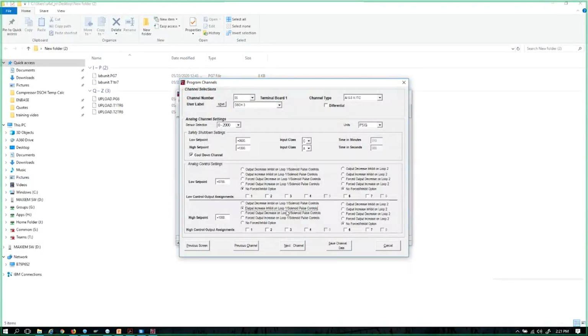Now what that's going to do is if my suction control valve is trying to open up to give more suction pressure, but I'm fixing to shut down on high discharge pressure somewhere up above 1,000 pounds, I can say when you hit 1,000 pounds, don't let the suction pressure come up any higher. Let it freeze in time. It can go down, but it can't come up. And we're talking about the position of a suction control valve or a suction control motor valve, if you will, if you like that terminology better.